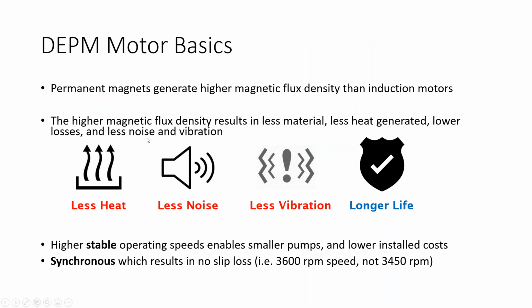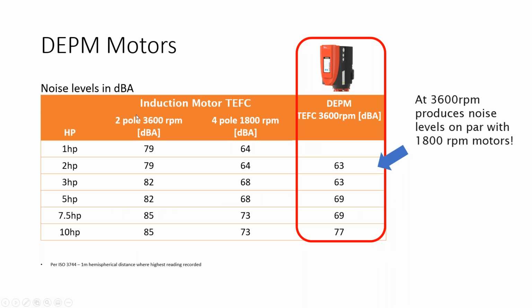Well, you know, back in the day, the two-pole motor 3600, you're right, a 5 horsepower motor would have been 82 dBs compared to an 1800, which was 68 decibels. Well, today's 3600 permanent magnet motor is coming in at 69 dBs. I challenge anyone to be able to differentiate between a 68 dB and a 69 dB motor in a boiler room. It's not going to happen. They're basically the same noise ratio.